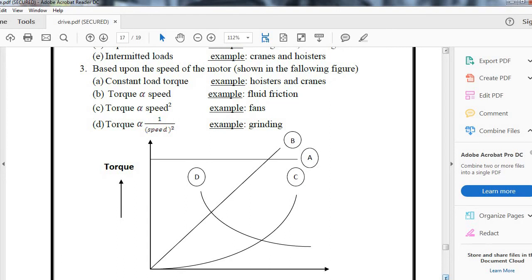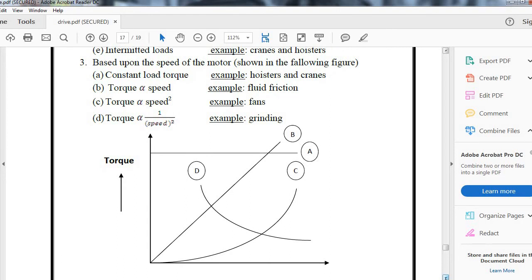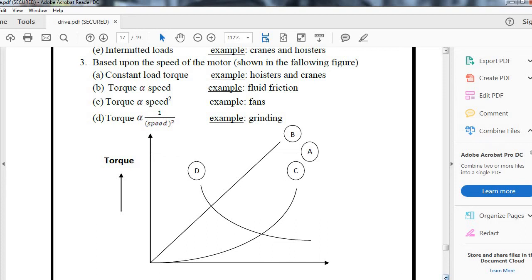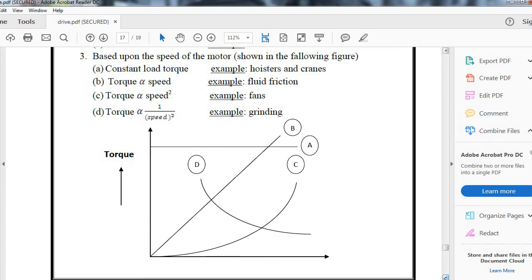This is the speed-torque characteristics where ABCD defines the torque-speed characteristics: A has constant load torque, B is linearly proportional to the speed, C is directly proportional to the speed squared, and D is inversely proportional to the square of the speed.